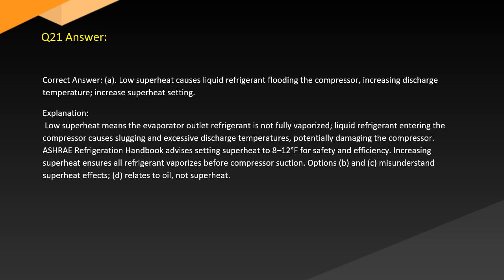Answer. Correct answer: A. Low superheat causes liquid refrigerant flooding the compressor, increasing discharge temperature. Increase superheat setting. Explanation. Low superheat means the evaporator outlet refrigerant is not fully vaporized. The liquid refrigerant entering the compressor causes slugging and excessive discharge temperatures, potentially damaging the compressor. The ASHRAE Refrigeration Handbook advises setting superheat to 8 to 12 for safety and efficiency. Increasing superheat ensures all refrigerant vaporizes before compressor suction. Options B and C misunderstand superheat effects. D relates to oil, not superheat.